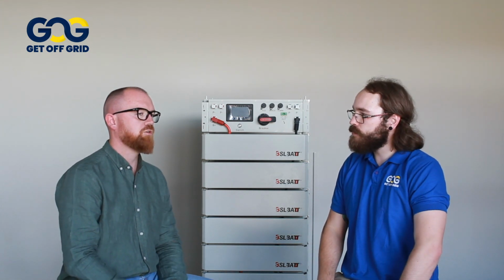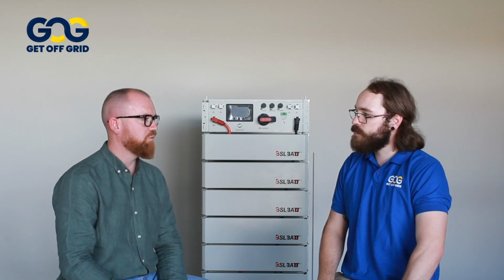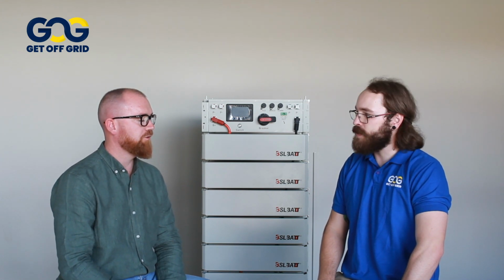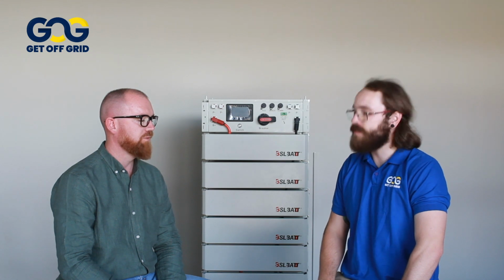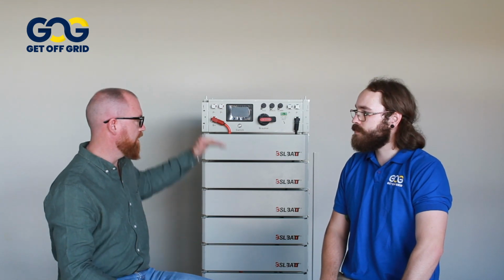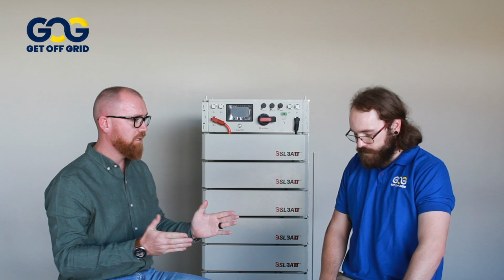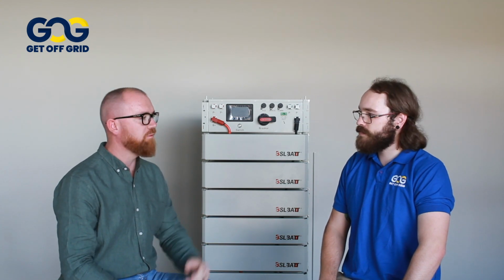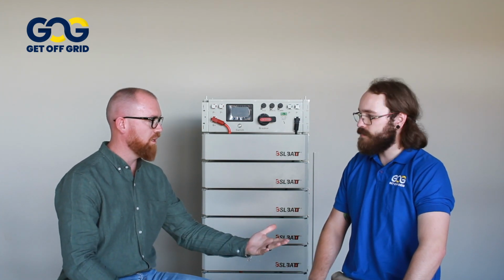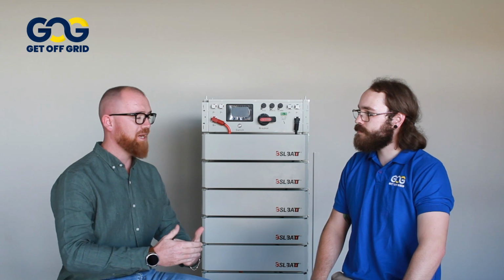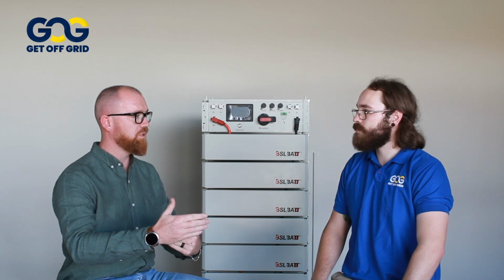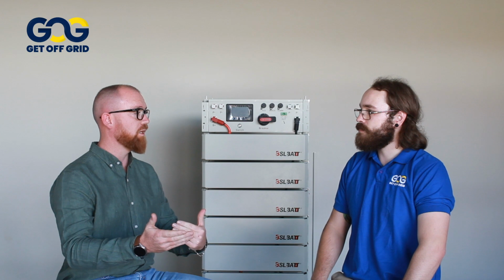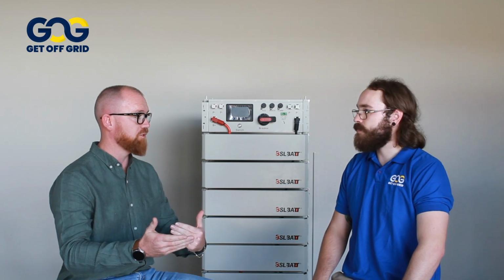So in layman's terms, each module is 7.7 kilowatt hours, that's 135 amp hours each. We can put 10 modules together to make one pack, and that pack will be 77.7 kilowatt hours, which we can then parallel to get between 300 to 400 kilowatt hours depending on project size and scope.